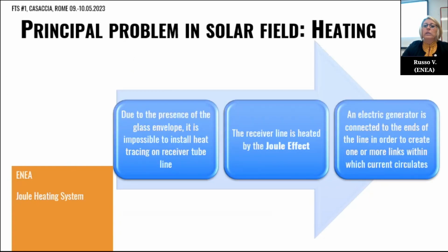As said before, another heating system is represented by the Joule effect. The Joule effect is applied on the loop of the solar field. In fact, due to the presence of the glass envelope on the receiver tube, it is impossible to install the heat tracing on this component. So the receiver and all the line are heated by the Joule effect. In particular, we have an electrical generator that is connected to the ends of the line in order to create one or more loops within which current circulates.